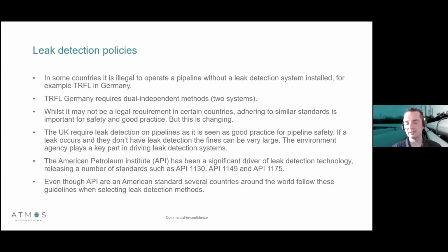So to pick an effective leak detection system, you need to look at your own pipeline, see what characteristics it adheres by, and then pick the solution that's best for you. The API 1175 came around, and this discusses the requirement that you need to look at leaks, thefts, and ruptures as three separate entities that can occur on your pipeline, and adhere technology to meet those needs. It also talks about that it's not good enough now just to have a leak detection system, that you need to constantly review and test that leak detection system.